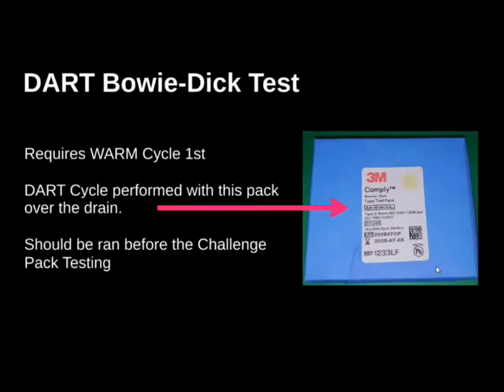So you always want to check your lot numbers and your expiration dates. The Bowie-Dick comes in the blue package. It always requires a warm-up cycle first. It's also performed with the pack right above the drain, and it should be run before the challenge pack in its own separate cycle.